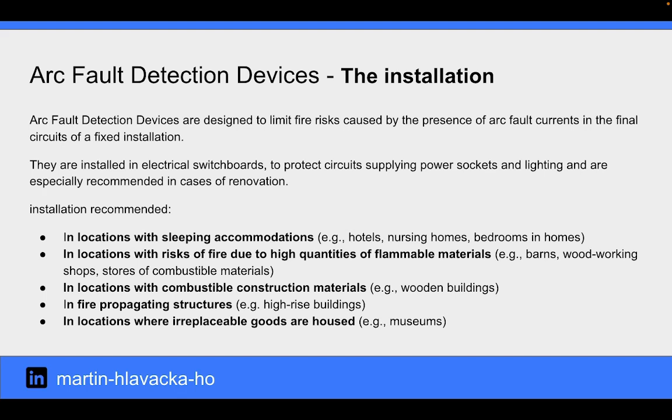In locations with sleeping accommodations such as hotels, nursing homes, and bedrooms in homes. In locations with risk of fire due to high quantities of flammable materials such as barns, woodworking shops, and stores of combustible materials. In locations with combustible construction materials like wooden buildings. In fire propagating structures like high-rise buildings. In locations where irreplaceable goods are housed like museums.